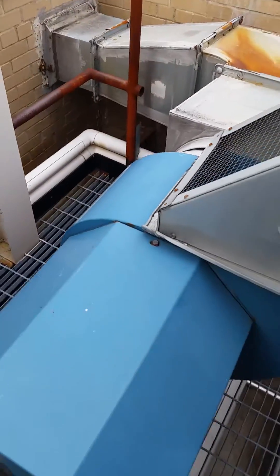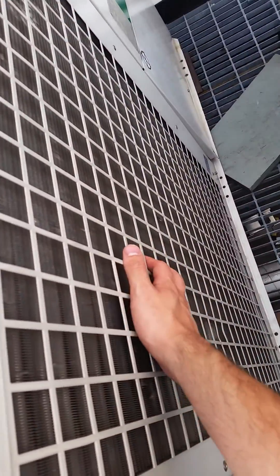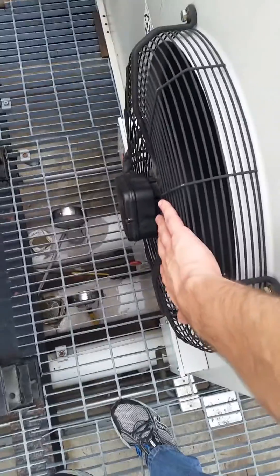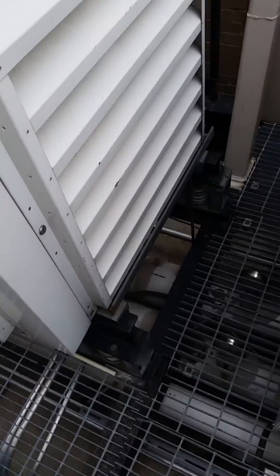This right here never works. I think this is an exhaust fan from the doctor's office, or it's an inducer fan for the boiler — I'm not sure. But that's going right into the condenser coil. This is going to run under high head pressure. And I've got this one blowing back out real hot air, going right near the chiller. That's lovely.